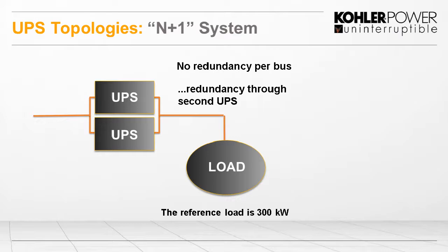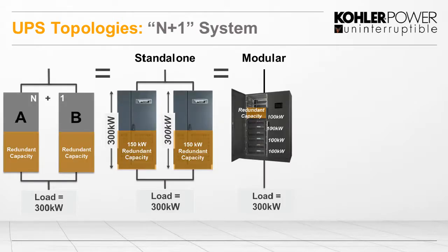So we look at the N plus 1 system here. Now, the actual load here, the same reference load of 300 kilowatts, has now got redundancy through the second UPS. So we have redundancy on that feed to the load. And again, we can make that up out of different systems. So we can either use two standalone 300 kilowatt UPSs, or we can use smaller modules, and in this example we have 4 100 kilowatt modules. Now if any one of those modules or one of the standalone was to be offline, the other one would take the required load. In normal operations they will be sharing the load. So as you look at the two 300s, they would each run 150 kilowatts each unless one was taken offline.